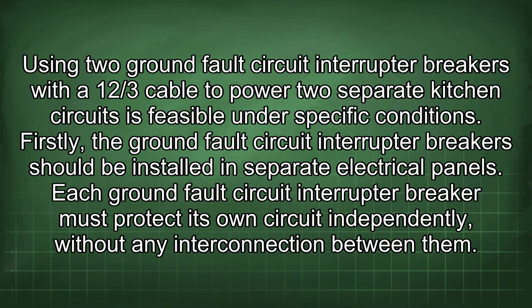Using two ground fault circuit interrupter breakers with a 12/3 cable to power two separate kitchen circuits is feasible under specific conditions. Firstly, the ground fault circuit interrupter breaker should be installed in separate electrical panels. Each ground fault circuit interrupter breaker must protect its own circuit independently, without any interconnection between them.